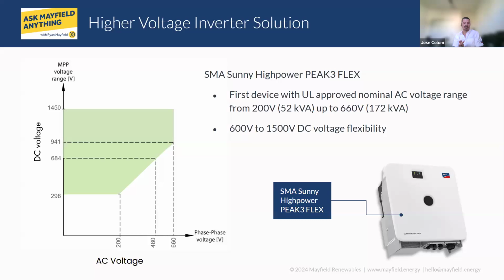What we are telling customers at this point is sometimes, hey, it might be good to add a transformer in between the 690 all the way down to, for example, 400 volts AC. Therefore, we can play within a good range for that DC voltage array, the 1,000 volt array that you have on site. So it gives us some flexibility, pointing out anywhere from 600 to 1,500 volts DC. And this is the solution that we specifically use for repowering. So it's the PEAK3 FLEX.